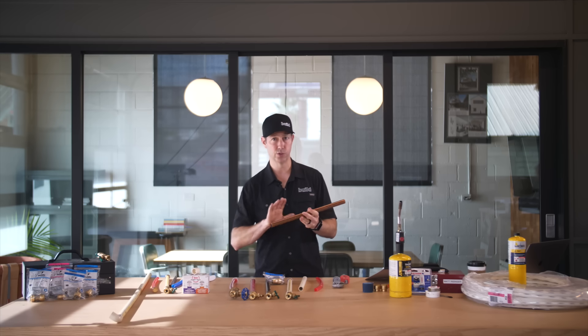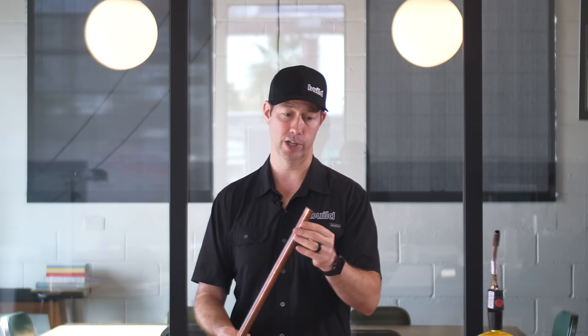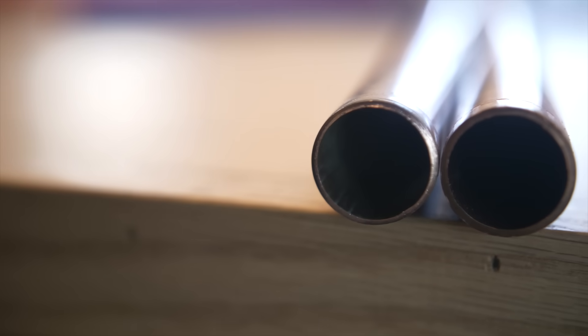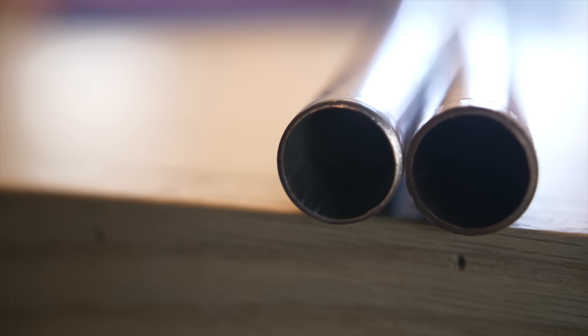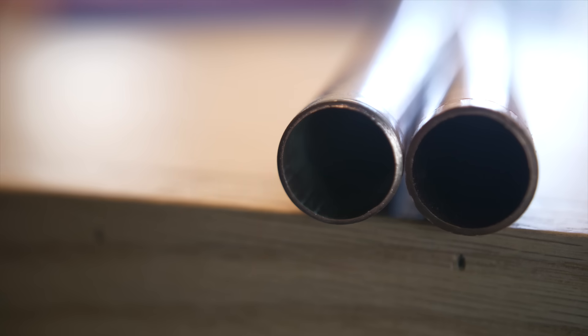There are two different types of copper: Type L and Type M. Type L is thicker-walled. For places like underground or a basement where there could be abrasion or corrosive conditions, you want the thicker Type L. Type M works just as well throughout the house, but I wouldn't bury it in the ground. Either grade will work fine for piping your house.